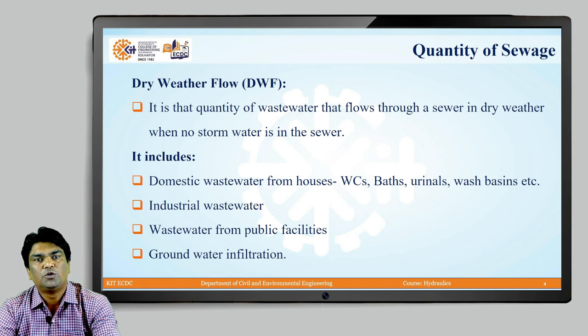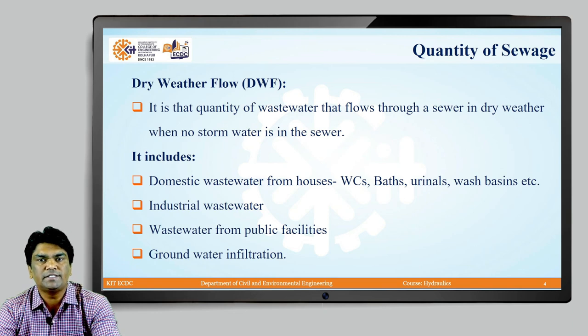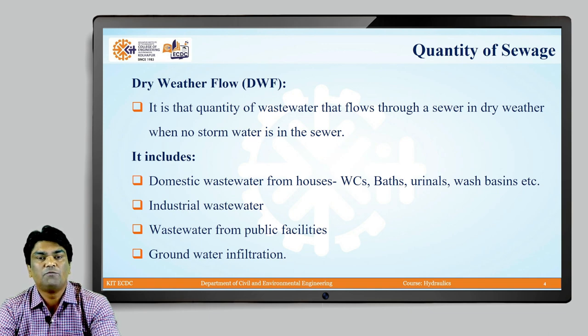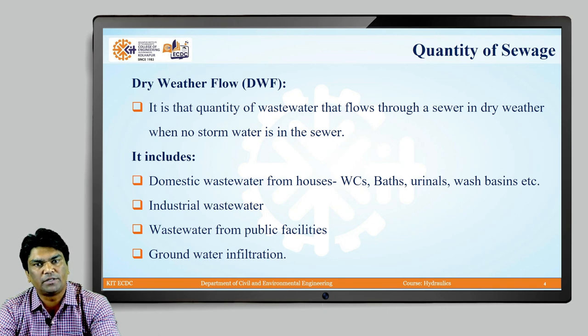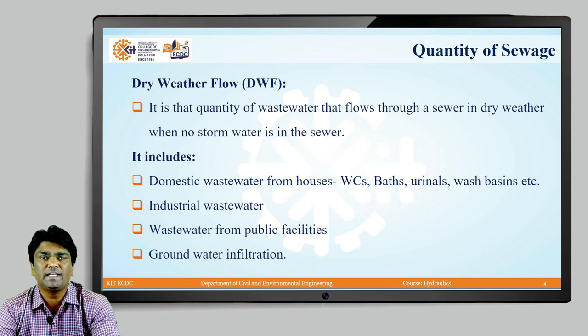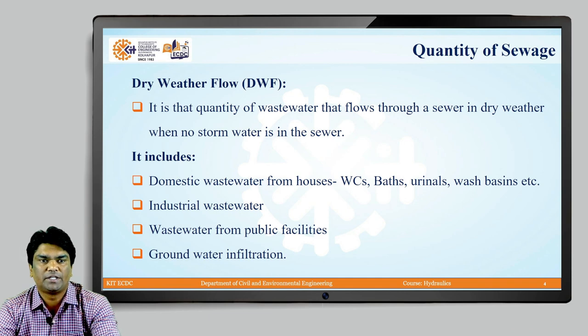Dry weather flow includes domestic waste water from sources such as water closets, bathrooms, urinals, and wash basins. Along with that, we also consider industrial waste water, waste water generated from public facilities, and ground water infiltration. We will also learn how to find out the infiltration quantity in further detail. These are the sources considered for finding out the dry weather flow; storm water flow is not included.